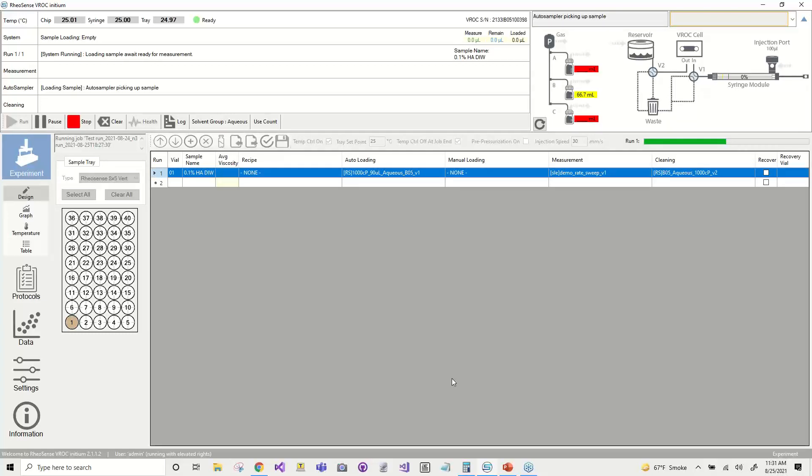While that's loading, someone is asking about measuring waxy crude oils and emulsions. When we've measured waxy samples in the past, it's very challenging to clean — it's not a testing problem, it's really a cleaning problem. So we would not suggest it on the automated system for now. That would be better for the manual systems where you have some flexibility to pump many different types of fluids, avoid tunneling, and allow for more soaking.